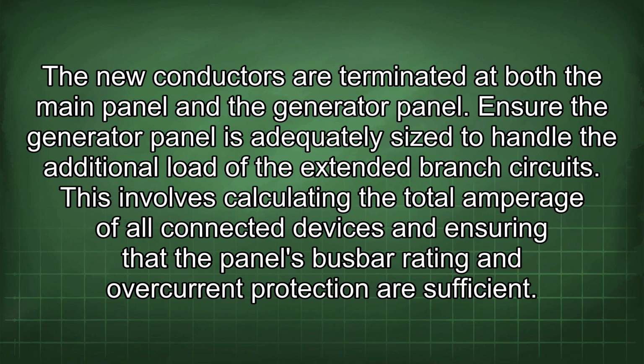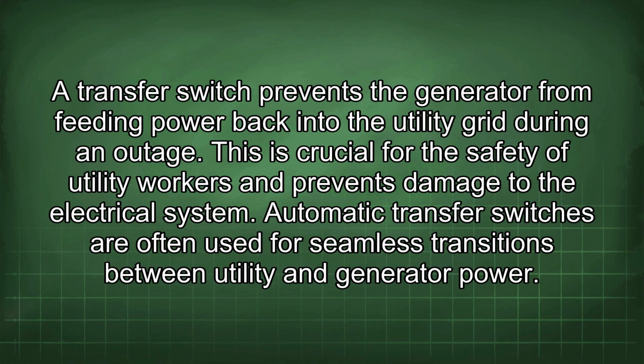Ensure the generator panel is adequately sized to handle the additional load of the extended branch circuits. This involves calculating the total amperage of all connected devices and ensuring that the panel's busbar rating and overcurrent protection are sufficient. A transfer switch prevents the generator from feeding power back into the utility grid during an outage. This is crucial for the safety of utility workers and prevents damage to the electrical system. Automatic transfer switches are often used for seamless transitions between utility and generator power.